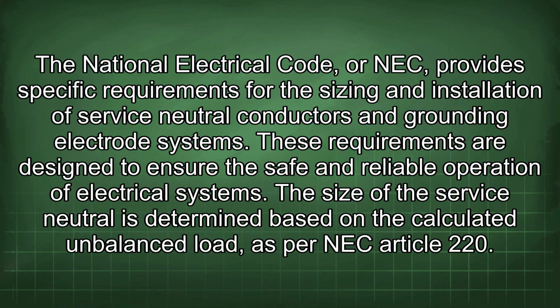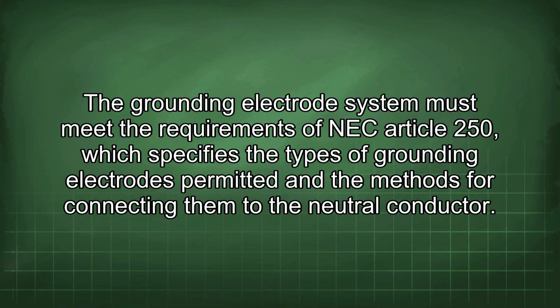The National Electrical Code, or NEC, provides specific requirements for the sizing and installation of service-neutral conductors and grounding electrode systems. These requirements are designed to ensure the safe and reliable operation of electrical systems. The size of the service neutral is determined based on the calculated unbalanced load, as per NEC Article 220. The grounding electrode system must meet the requirements of NEC Article 250, which specifies the types of grounding electrodes permitted and the methods for connecting them to the neutral conductor.